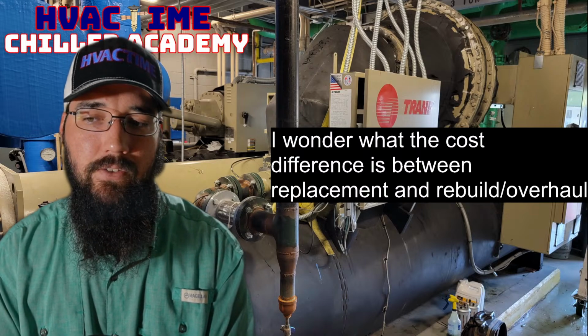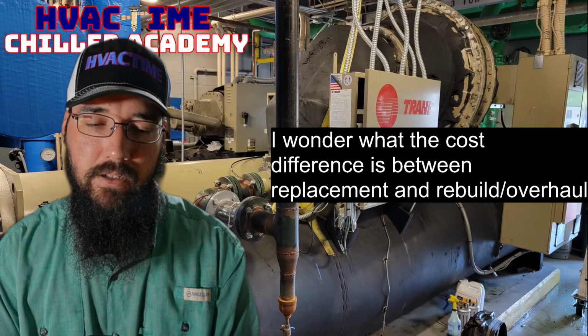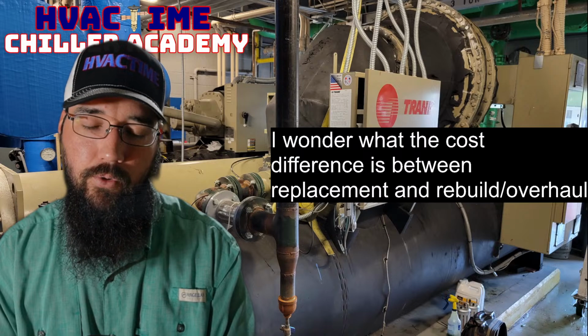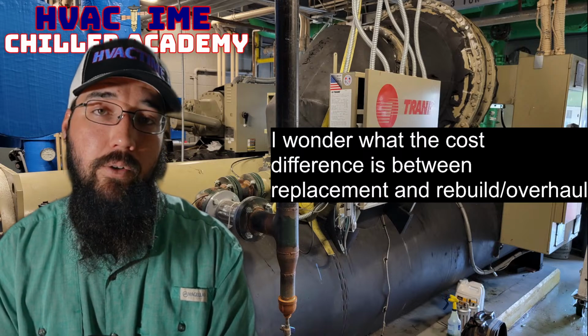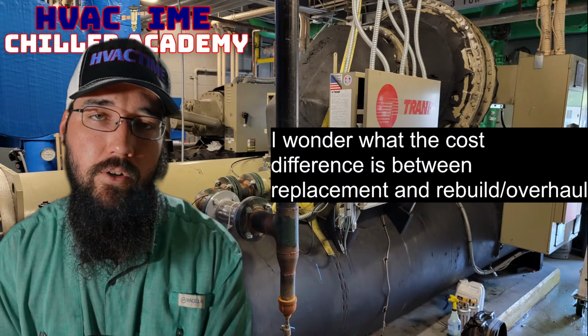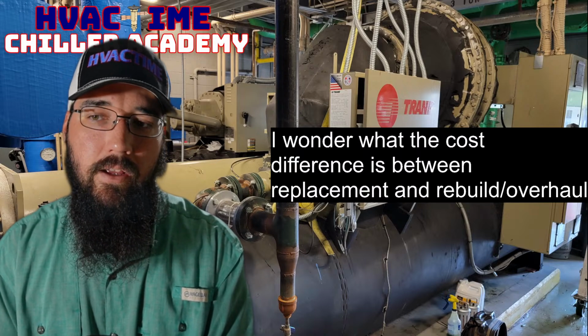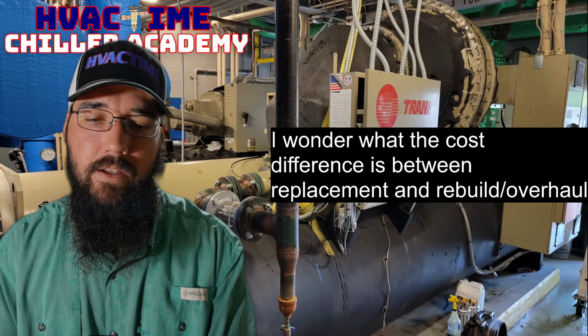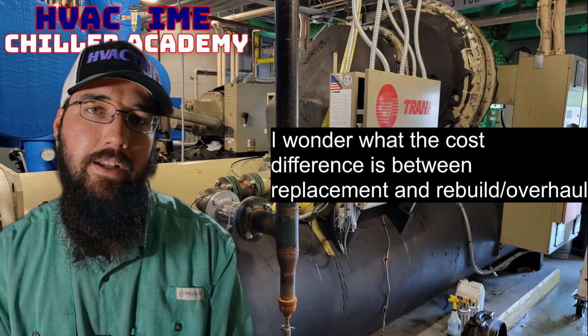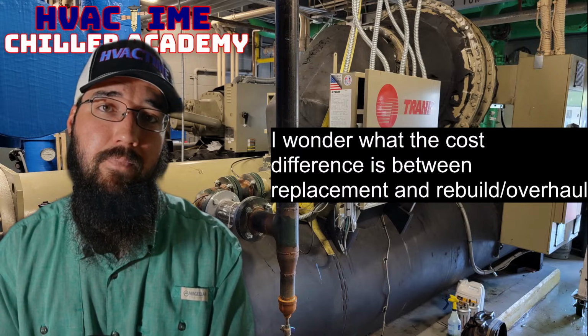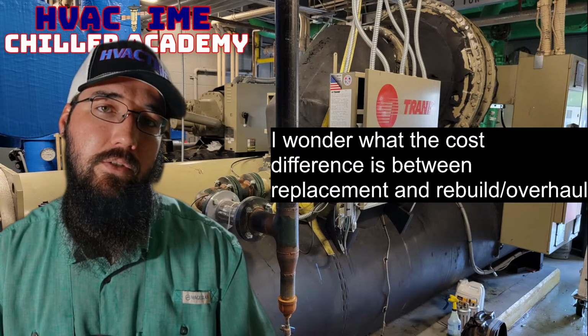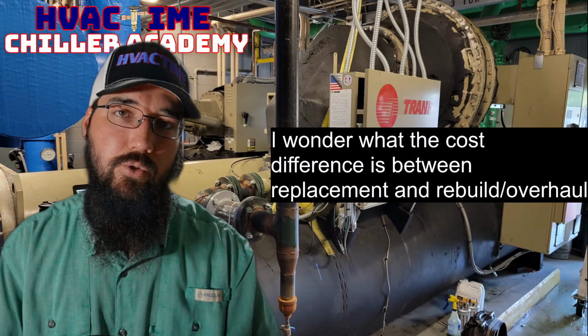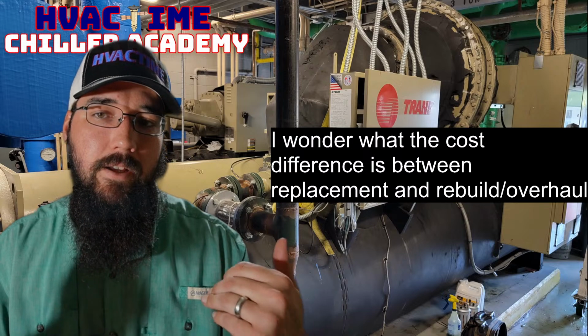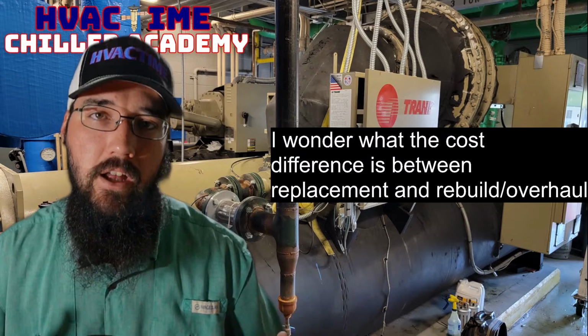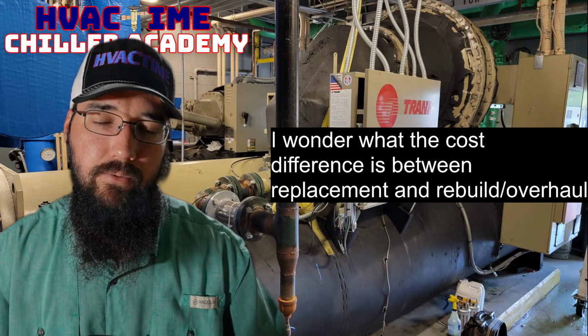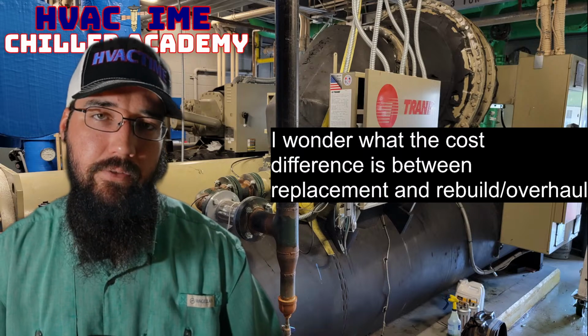So would it make sense to completely strip down and rebuild an RTU, a split system at somebody's house, or even most air-cooled chillers? The answer is no. The conditions those chillers operate in put a lot more stress on them because they're out in the elements most of the time, whereas these water-cooled centrifugals are usually out of the elements, so they have less wear from that perspective.